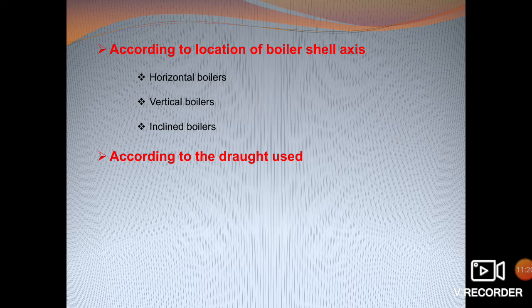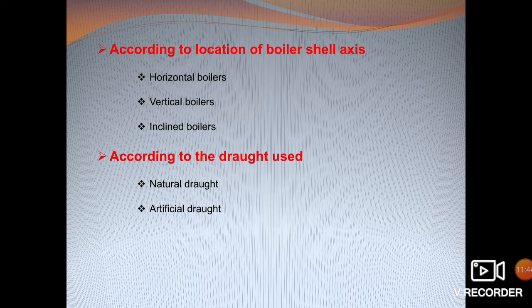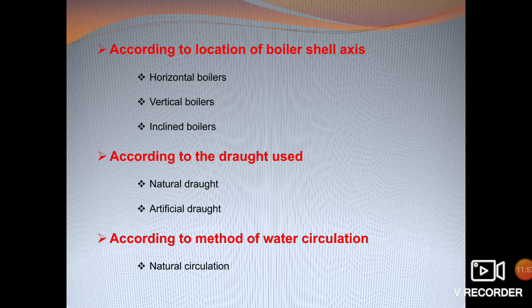According to the draught used, boilers are classified as natural draught boilers, where air circulation for combustion is provided with the help of a chimney, and artificial draught boilers, where either a forced draught fan or an induced draught fan or both are used to provide the airflow. According to the method of water circulation, there is natural circulation — where circulation occurs due to density differences caused by water temperature — and forced circulation, where circulation is done with the help of a pump.